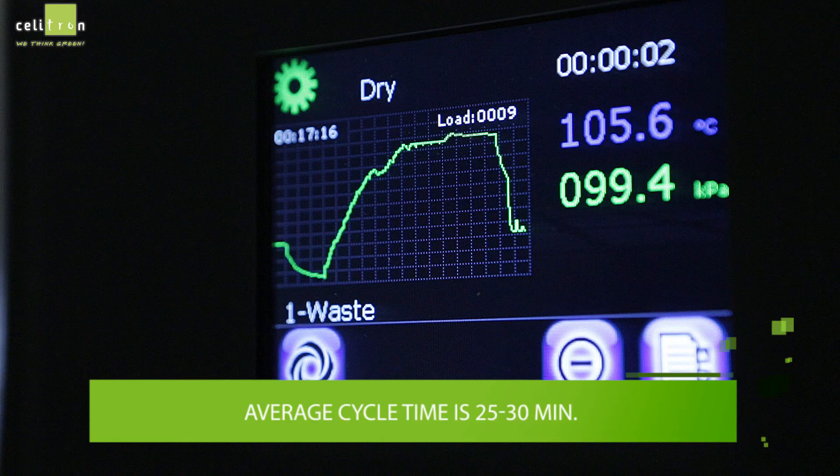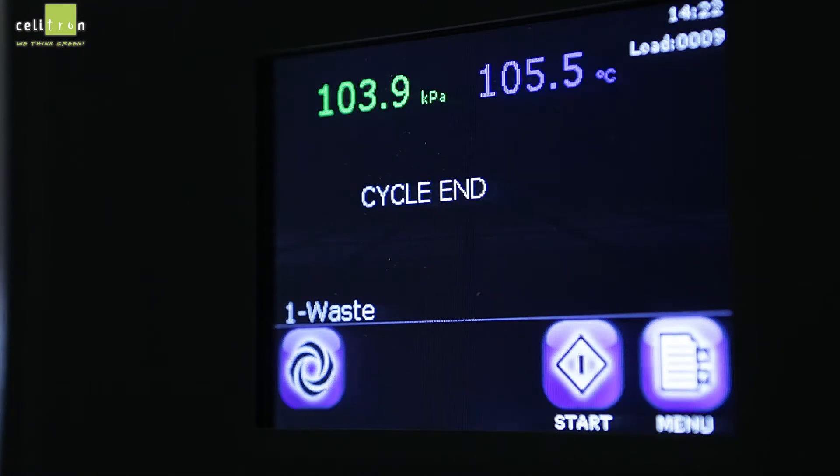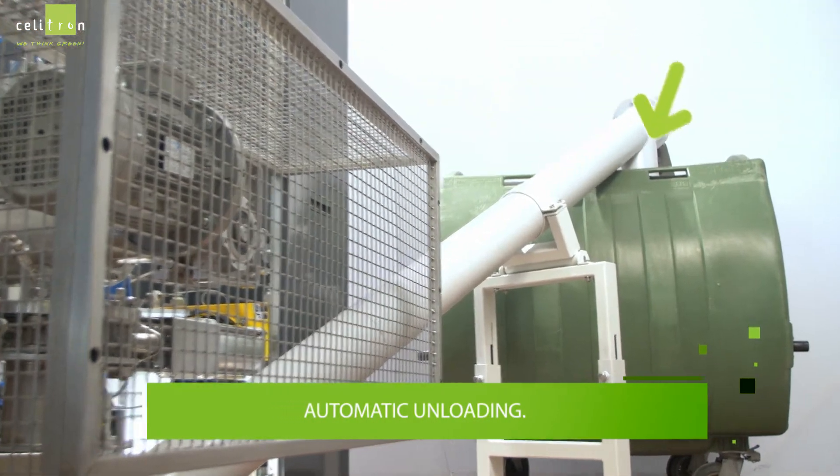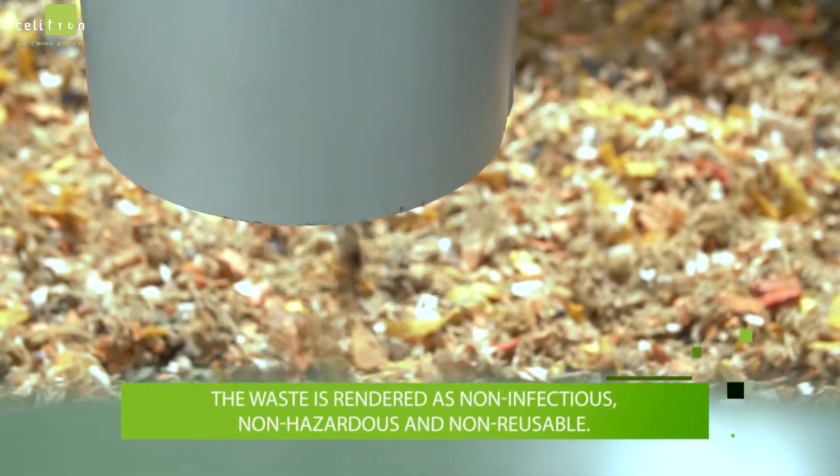The average cycle time is 25 to 30 minutes. Then the unloading starts with automatic discharge via the conveyor into the waste container.